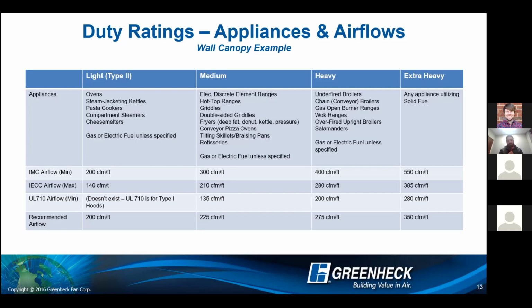And keep in mind, just like anything with UL, these are minimums based on perfect lab conditions. So if in a perfect lab condition, we were able to do 200 CFM per foot, that's probably not going to be enough CFM when we actually get into the field and we have cross drafts and we have cooks walking in front of the kitchen and we have pass-through windows. That's probably not going to work.